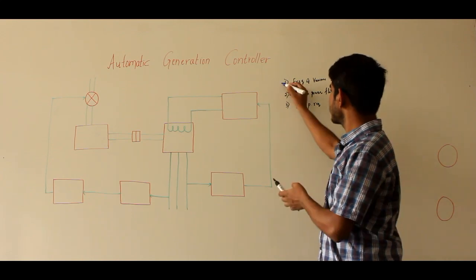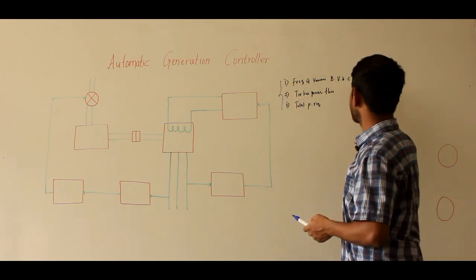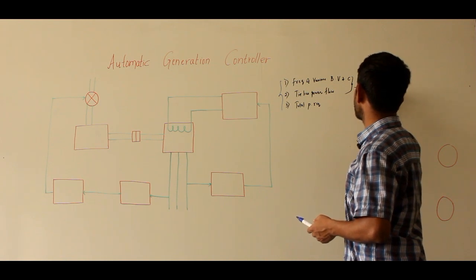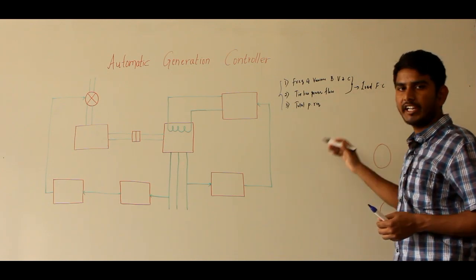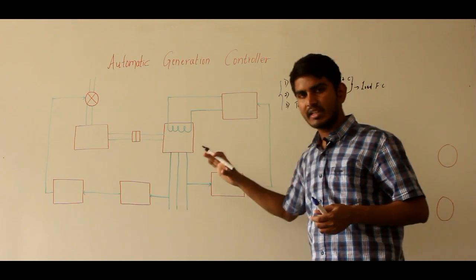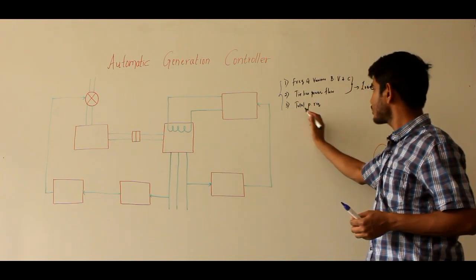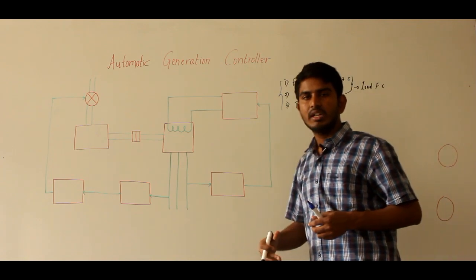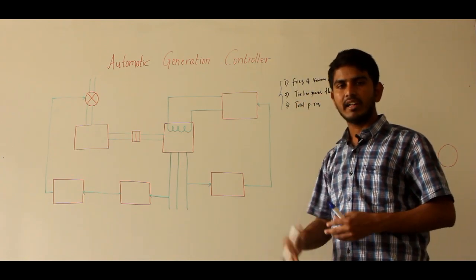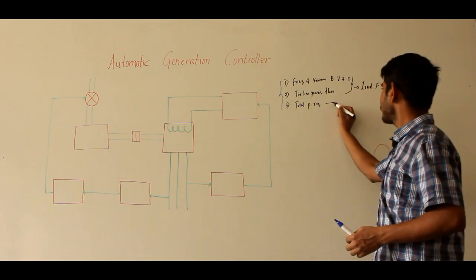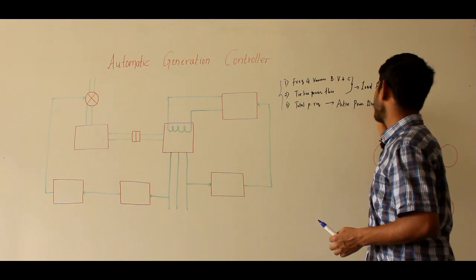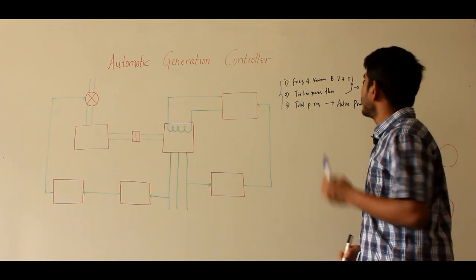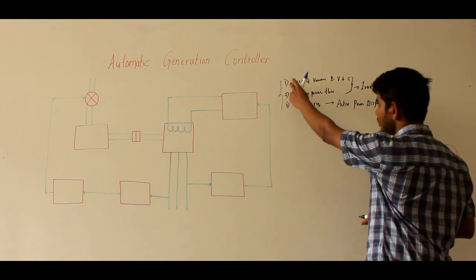AGC ensures these three functions. The first two functions — frequency of various bus voltage and current, and tie-line power flow among the interconnected areas — will be carried by load frequency control. The third function — total power requirement on the whole system must be shared by individual generators at an economically optimal fashion — will be carried by another set of control called active power dispatch, which we are not discussing here.